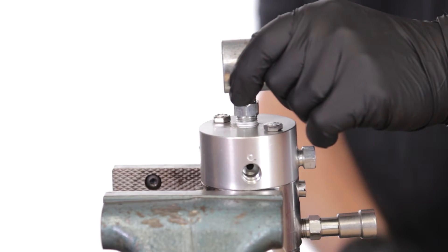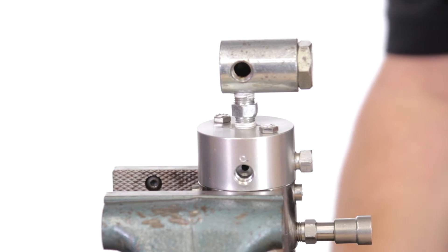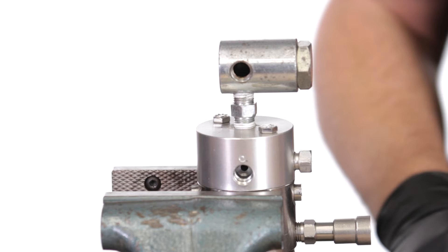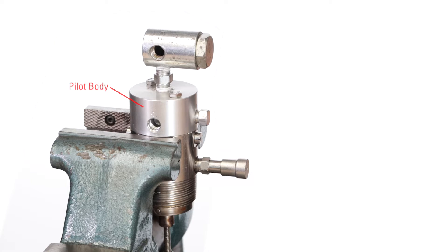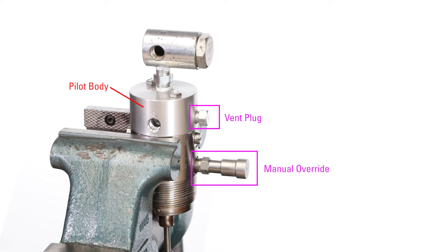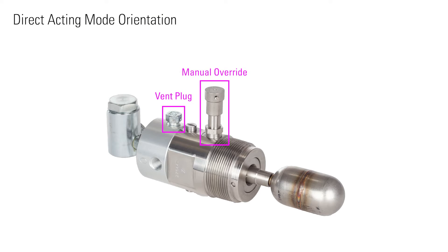If you are unthreading the switch from the vessel, place the switch in the vise, but tighten only on the flats so that you do not damage the threads or housing. Note the orientation of the pilot body. If the vent is on the same side as the manual override, it is set up in the direct acting mode. If you're not changing applications, you'll want to make sure to assemble this in the same orientation later.